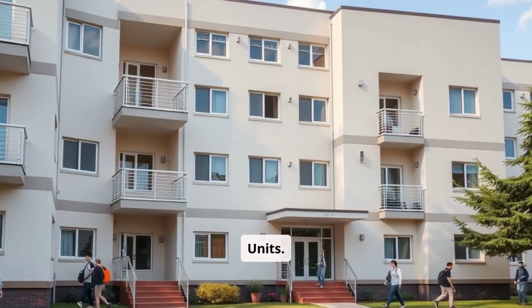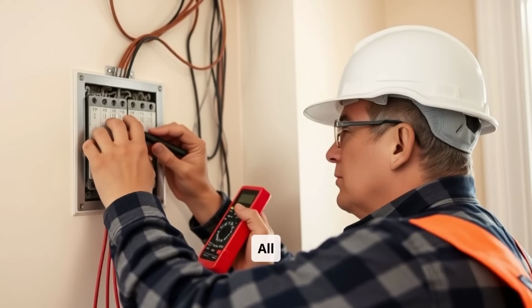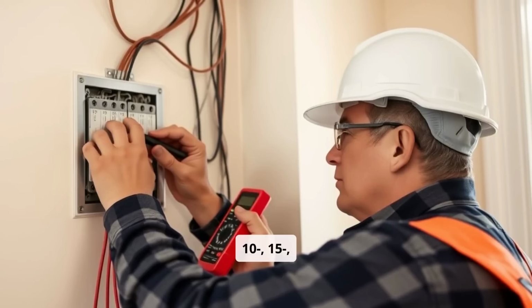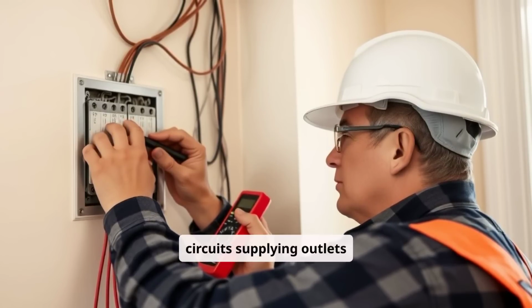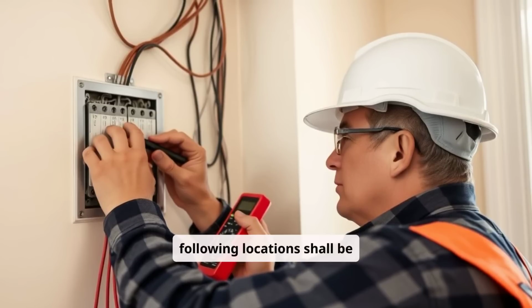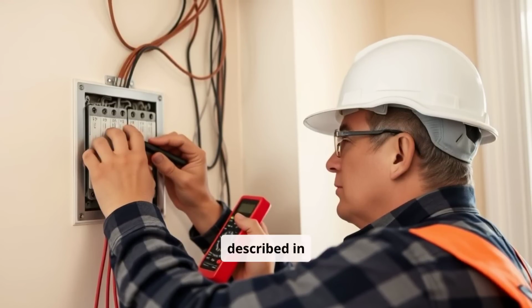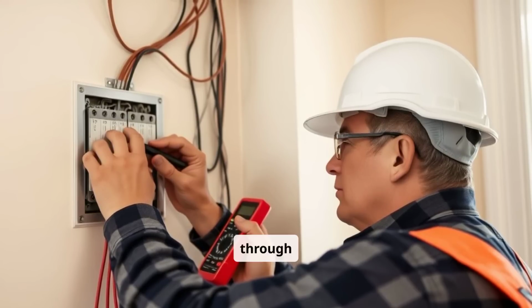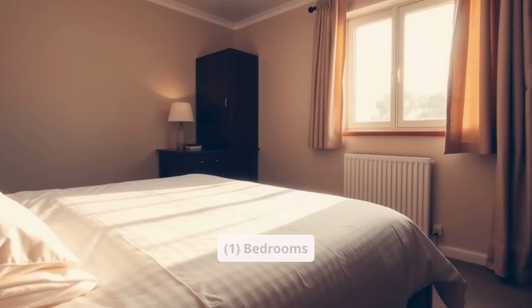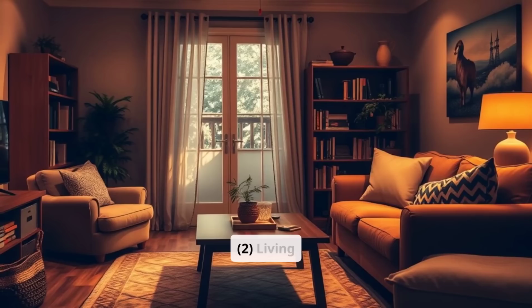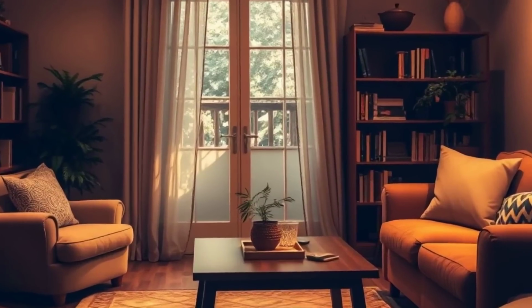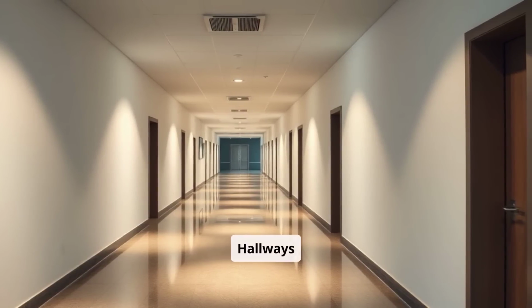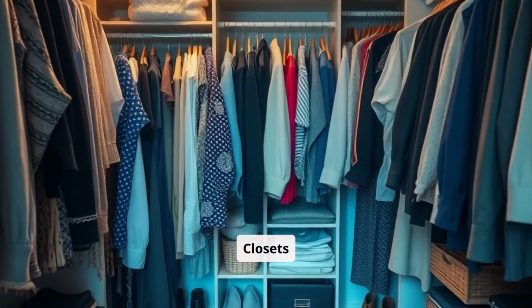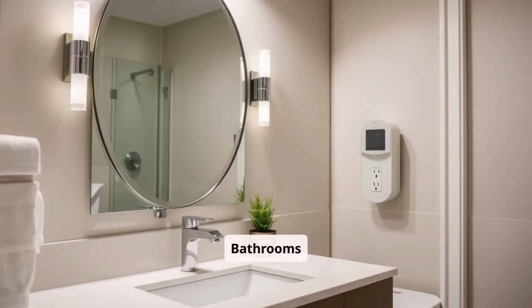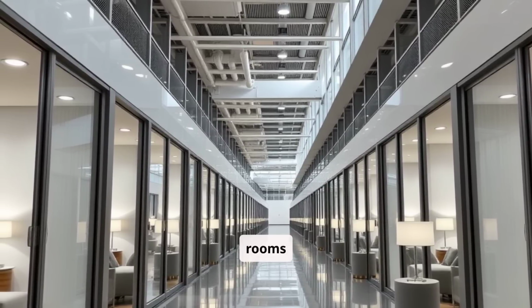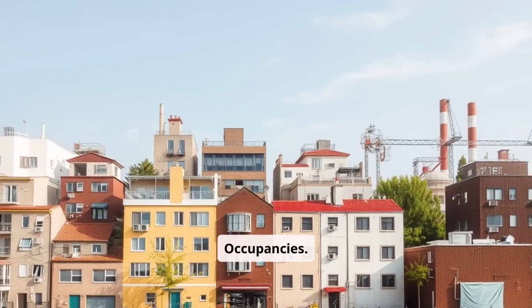C. Dormitory units. All 120 volt, single phase, 10, 15, and 20 ampere branch circuits supplying outlets or devices installed in the following locations shall be protected by any of the means described in 210.12(A)(1) through (A)(6). 1. Bedrooms. 2. Living rooms. 3. Hallways. 4. Closets. 5. Bathrooms. 6. Similar rooms.